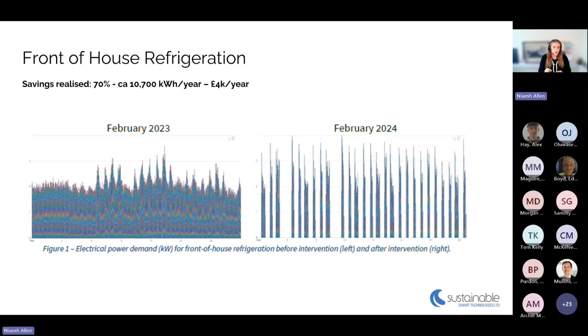So we said to them, can I look at your wider energy for the building? This is where I think the bigger opportunity is. They let us do some sub-metering, we put in some CT clamps, and we took them from just an energy bill to knowing exactly where the energy went within the building - how much energy on a show day, a non-show day, and night time, and where that energy went. It is quite small to see here, but it's showing lighting, front of house, dressing rooms, pump systems. However they wanted it broken down is how we did it.